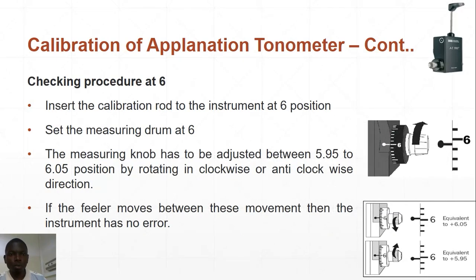We are checking the procedure at 6. Insert the calibration rod into the instrument at the 6 position. Set the measuring drum at 6. The measuring knob has to be adjusted between 5.95 to 6.05 position by rotating in clockwise or anti-clockwise direction. If the feeler moves between these movements, then the instrument has no error.